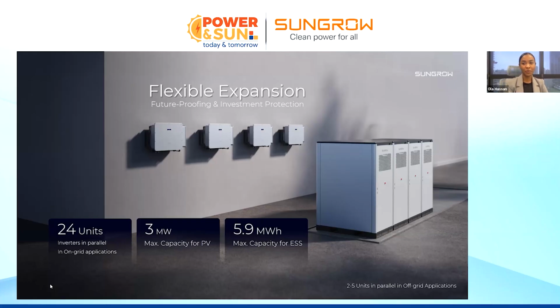Again, one of the questions that is recurring: why are we using the energy storage in case of on-grid applications? We say we can connect up to 24 units in parallel. As I mentioned earlier, it's because we're trying to maximize our self-consumption, maximize our reliance on our own PV system, reduce our reliance on the grid, and therefore reduce the electricity bills and the electricity consumption. And we can connect between 2 to 5 units in parallel in off-grid application. This is in standalone off-grid applications with the hybrid inverter.